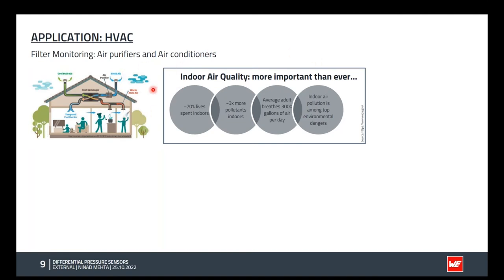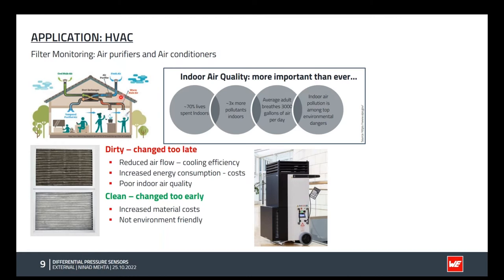So every HVAC system has a filter so that you get clean air inside. And with time, the filter gets dirty, and it is very important that you change the filter at the right time. For example, if you change the filter too late, then your filter is too clogged and you might not have enough airflow, and your cooling or heating efficiency is not enough. This will also lead to higher energy consumption and higher costs. And in the end, because the filter is not fully functional, you will have a poor indoor air quality.